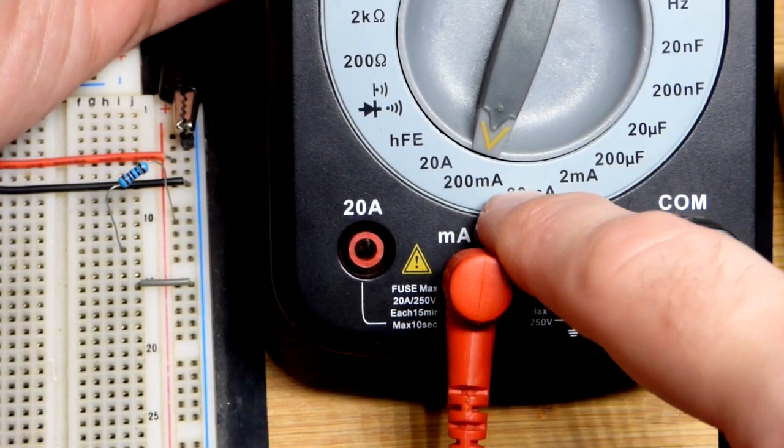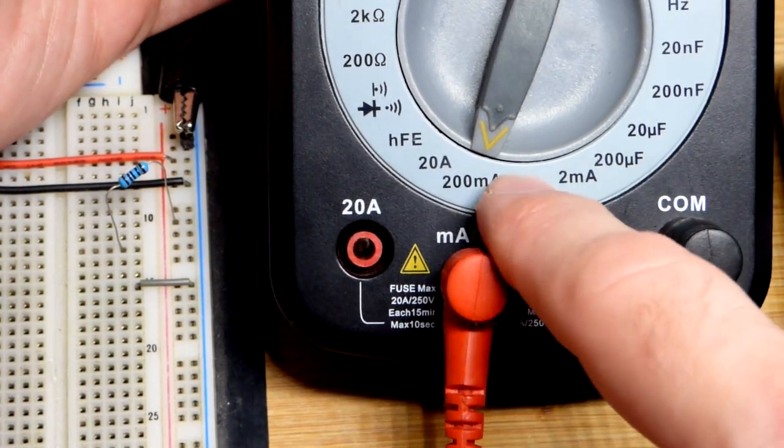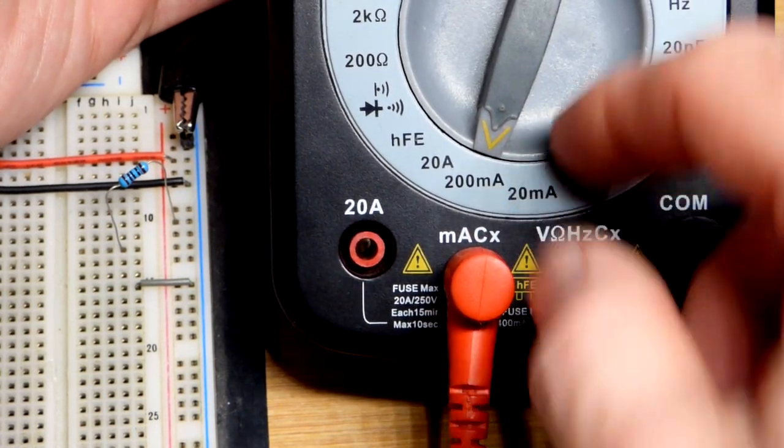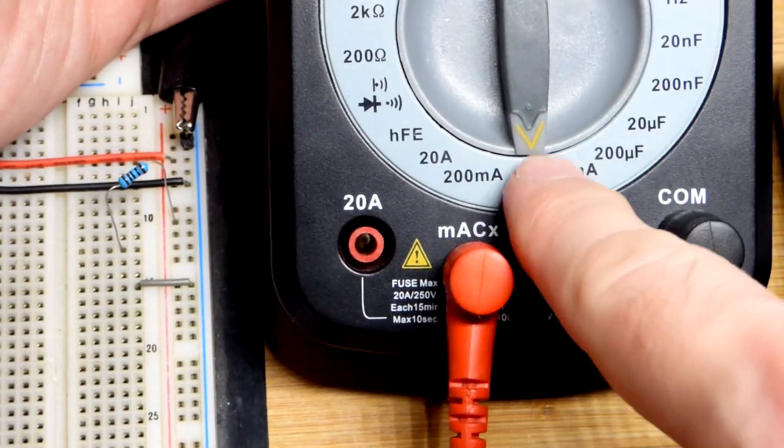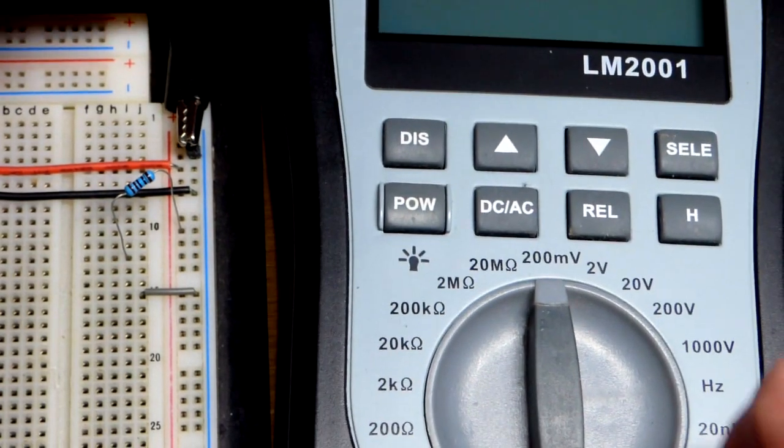We need to set the meter to a higher current than we're going to measure. There's fuses in here, and the fuses will blow if you measure more current than the meter is set to. We're going to set it to 20 milliamps, more than we need, but it'll save time instead of working our way down.